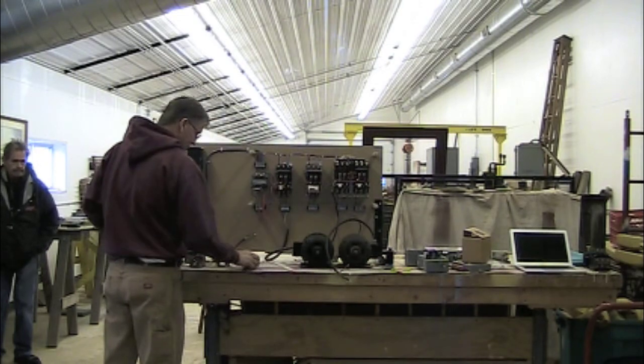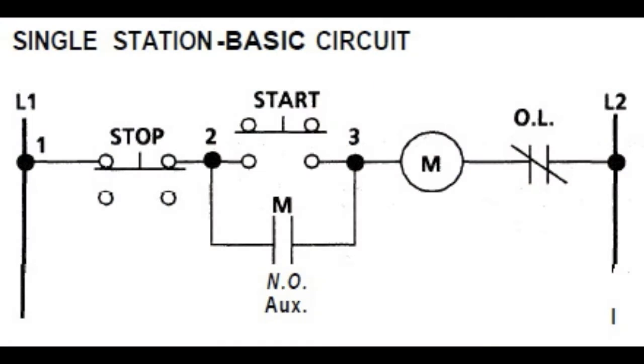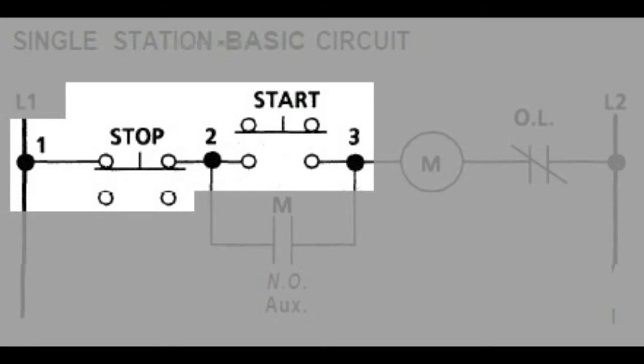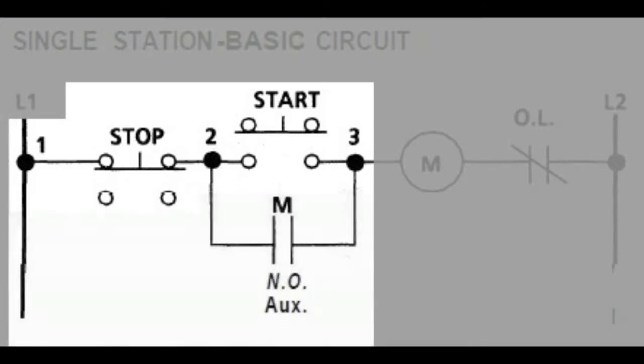Okay, so on the starter side of the 3-wire, I don't know if anybody can see this. This is usually how things are laid out when they show you how to hook them up. The standard convention is you're always going from line one, and the first thing you go through is the stop button. This is all just in series. It's the normally closed stop button in series with the normally open start button, in series with the coil, and then the overloads, and then to the other side of the power. If we push the button, it's going to close the circuit, the contactor is going to close, and the motor is going to run. But if we release the start button, nothing's going to happen. So the auxiliary contact set is actuated by the contactor. When it closes, it completes the circuit and holds the control circuit shut. When you release the button, everything's continuous. It doesn't release until you push the stop button.